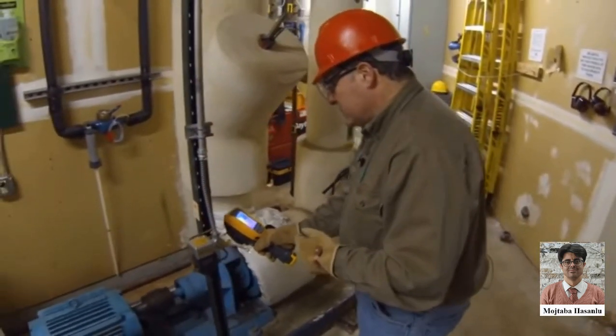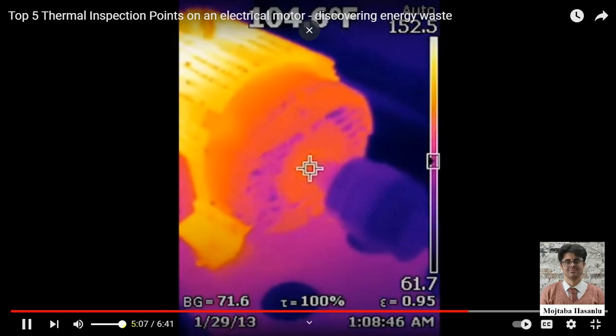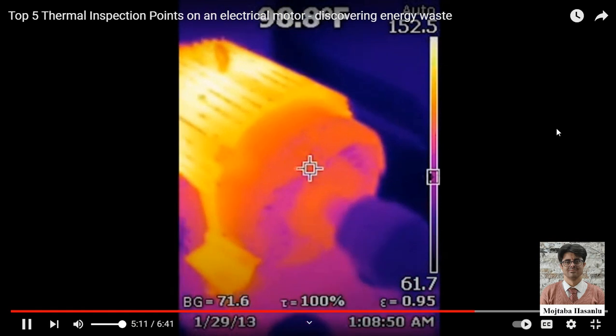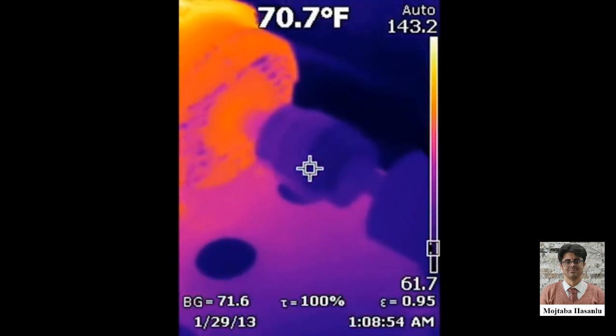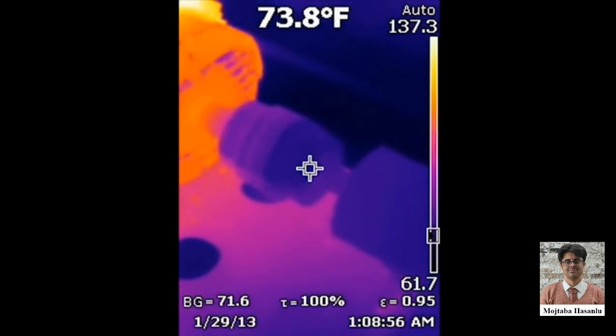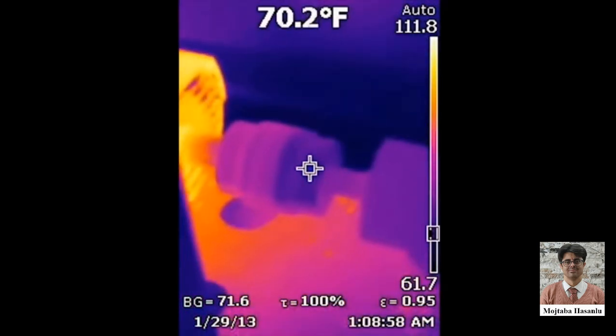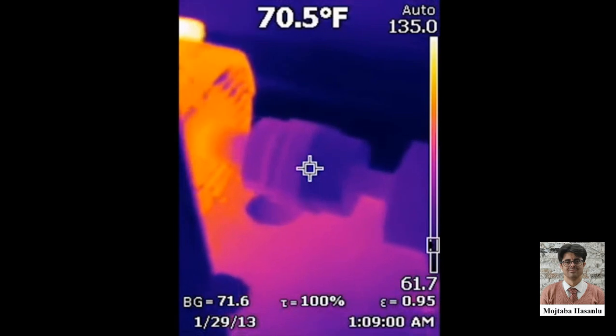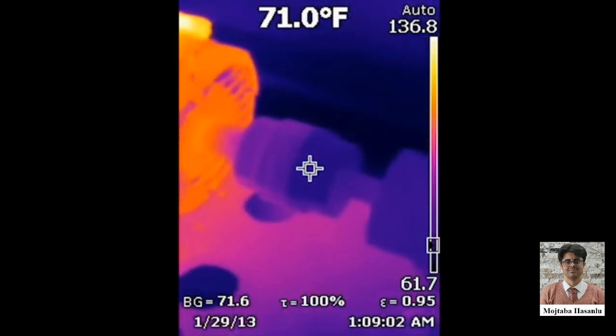I see a little bit of extra heating around the motor side of the coupling, but that could be an emissivity issue. I don't really know at this point. I'm not seeing anything significant. And because I'm not seeing any excessive heating on the bearing of the motor itself, that tells me more than likely the alignment's probably pretty good on here.